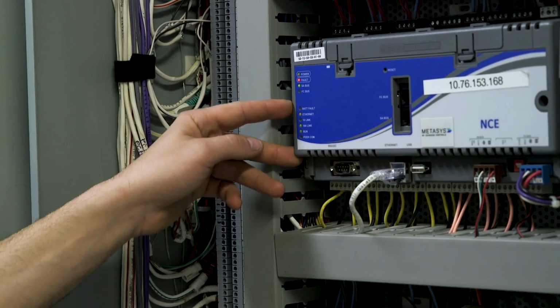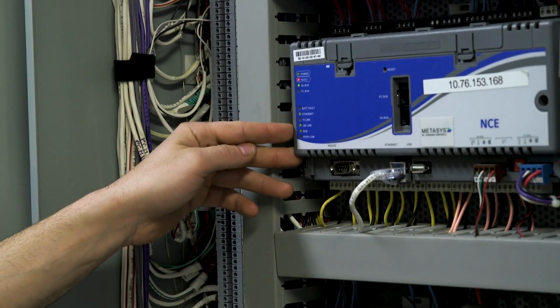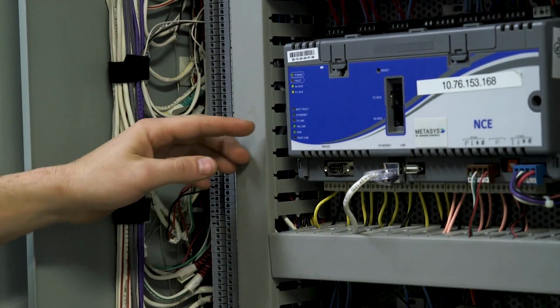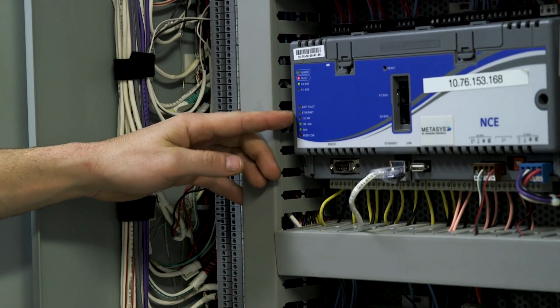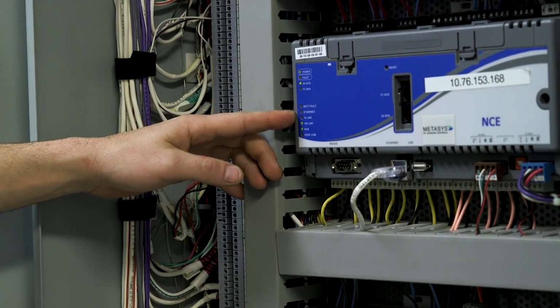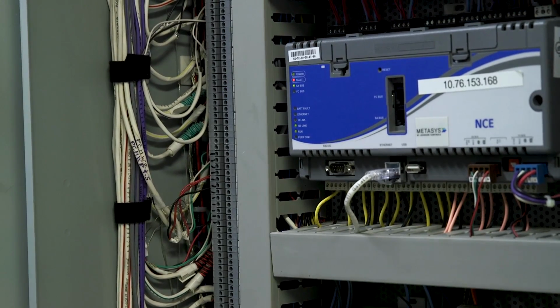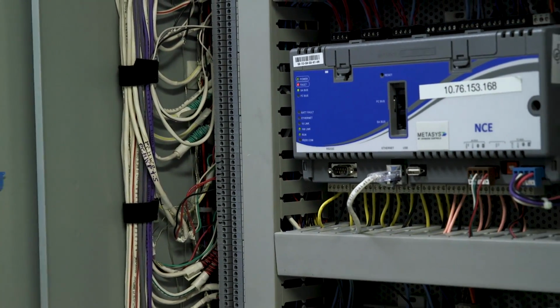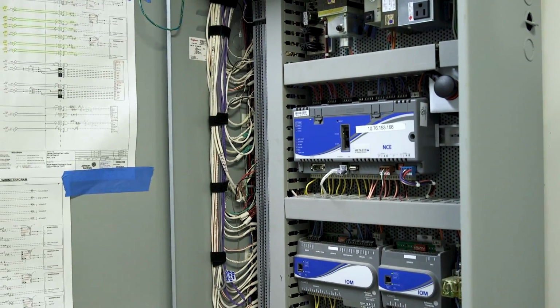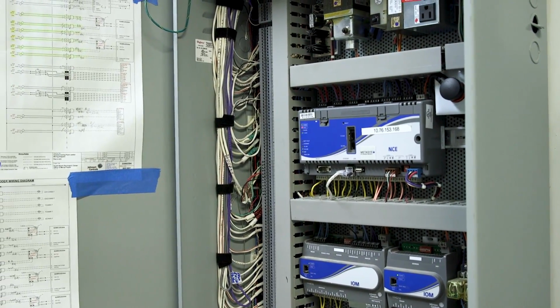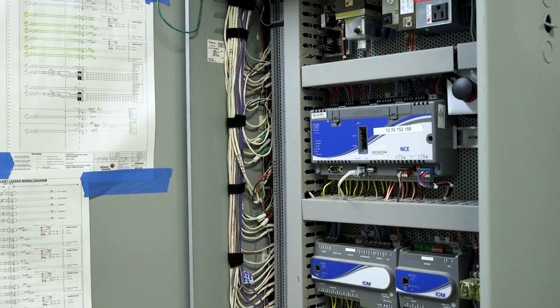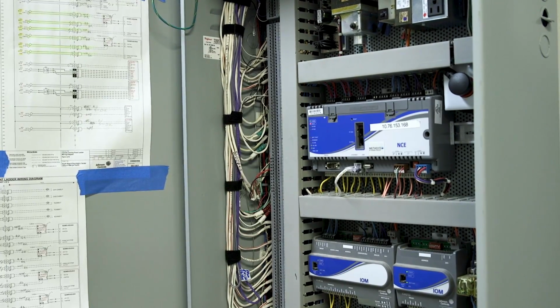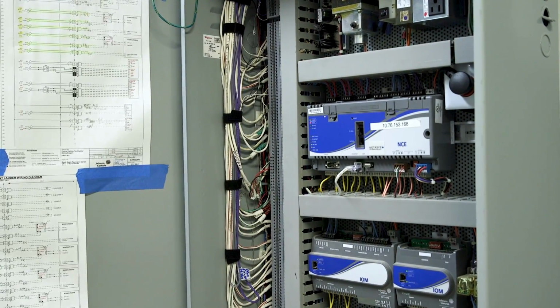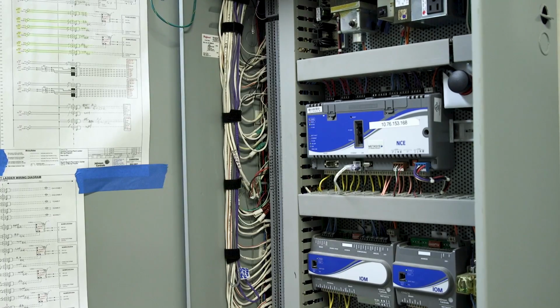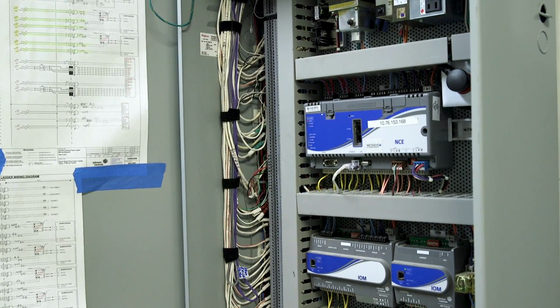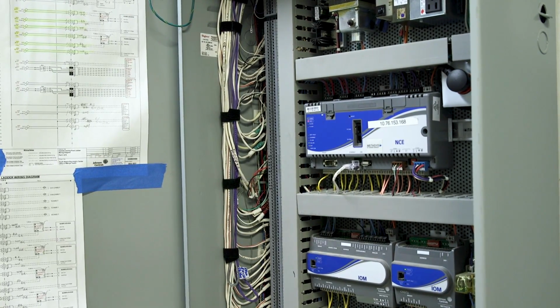Then this is just your connectivity lights, showing what speed you're running at, making sure your Ethernet is blinking, which means you've got connectivity. This is burned-in memory - things like certain programs, certain settings, what address am I, everything is burned in the EEPROM. That battery keeps the EEPROM, so when you lose power, it helps keep that memory. Like right now, if you pulled the battery out, it wouldn't do anything, only because you're on live power.